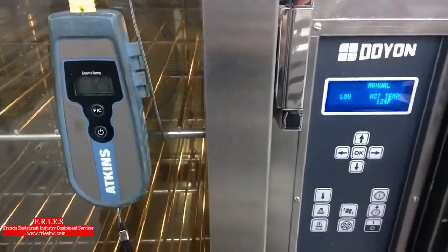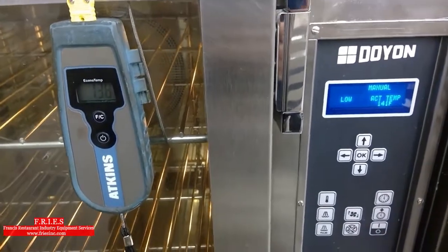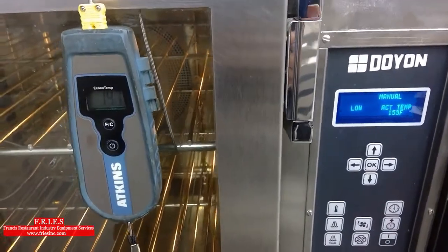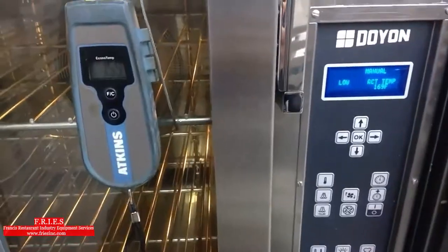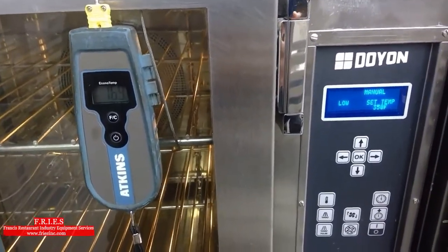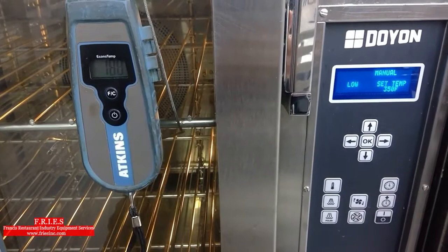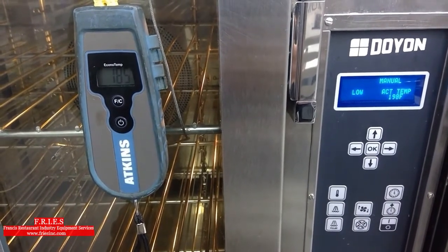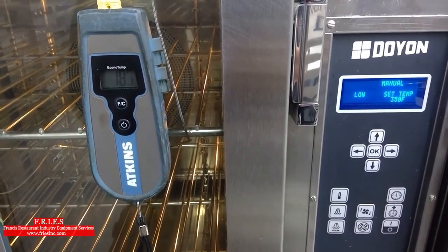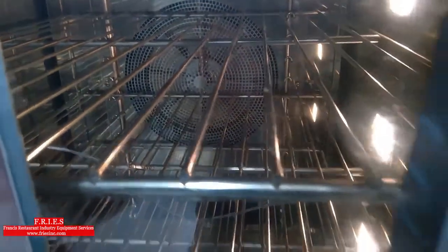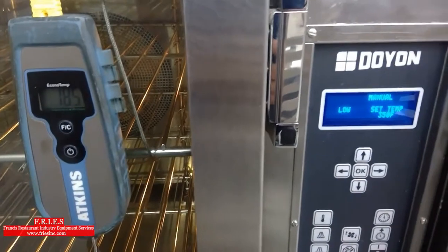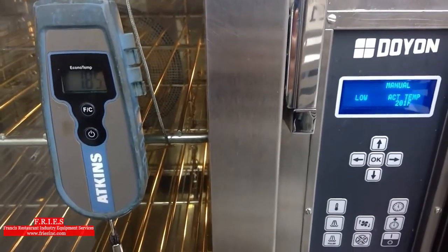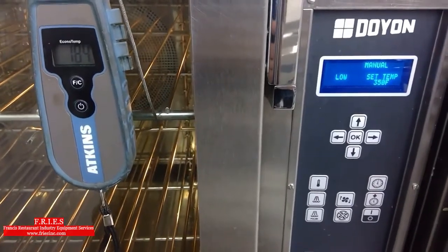I'm just going to hit fast forward here, just because it takes a little bit of time for this thing to heat up. Alright, so the blower motor just shut off. Anytime that shuts off, the burner's going to shut off as well. So every few minutes, that blower will change rotations.